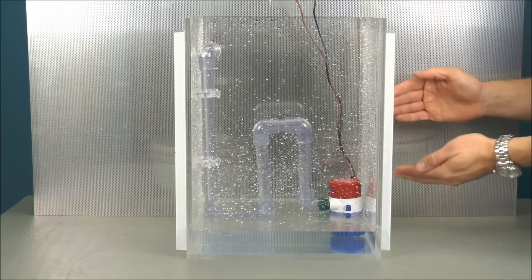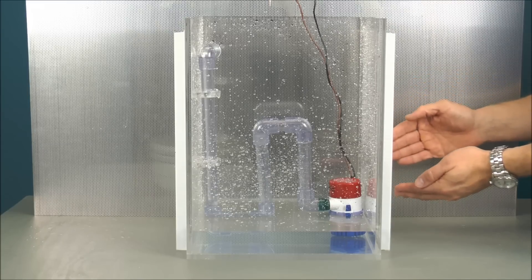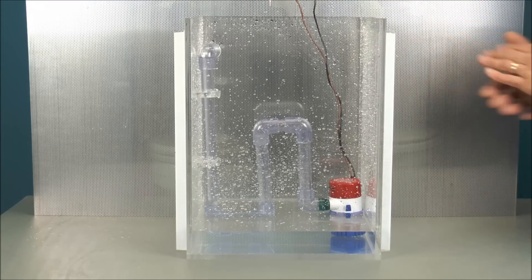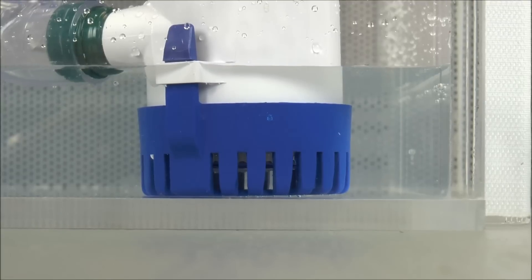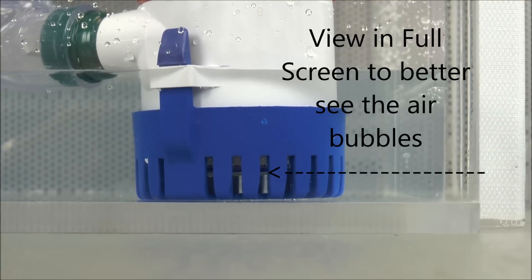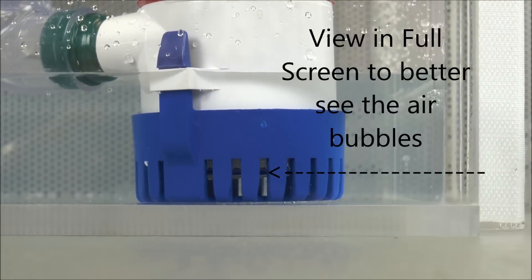Which means the water has to be in contact with the impeller to be able to pump the water out. That's a great example of an airlock right there. See that big air bubble on the underside of that running pump?